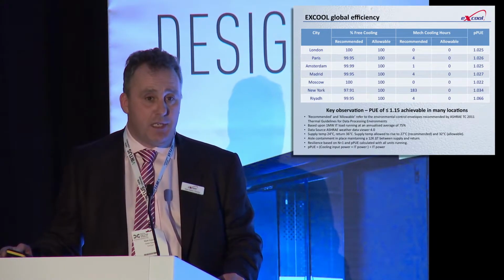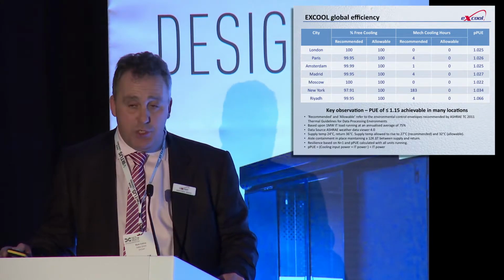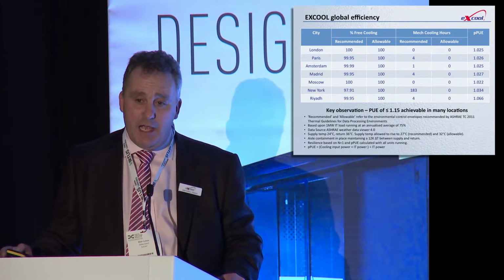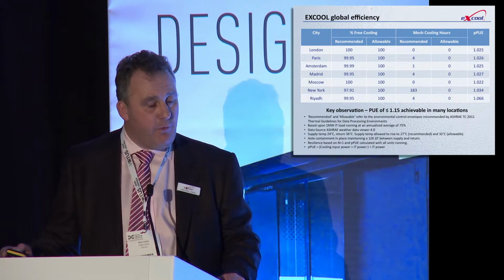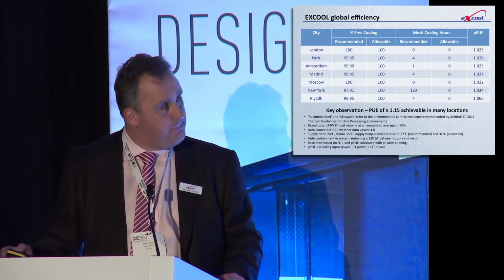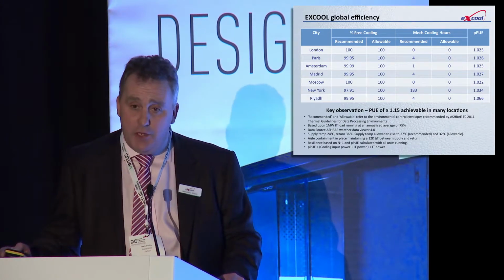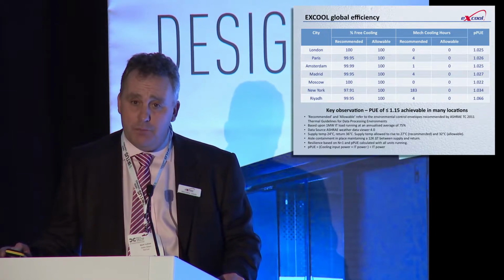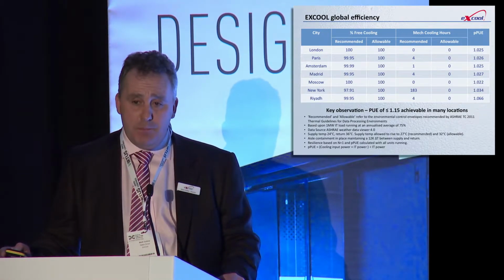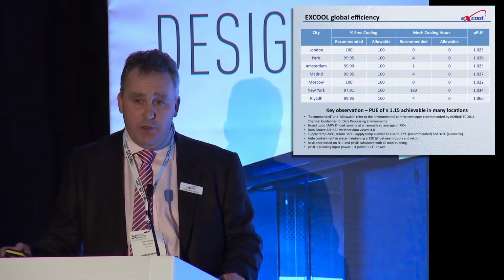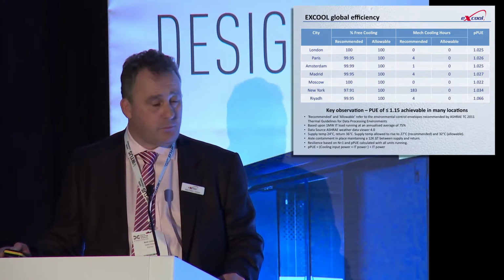There's some real surprises up there. Places like Riyadh, yes, we do need compressors to maintain ASHRAE recommended, but they only run for 4 hours per year. Certainly in London, we don't need any compressors at all. So it's all fans and pumps is all we need to cool the data center down.